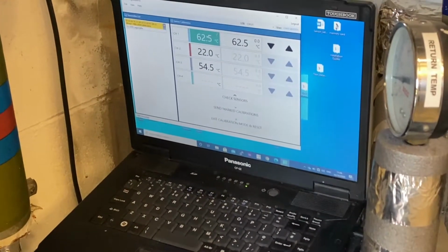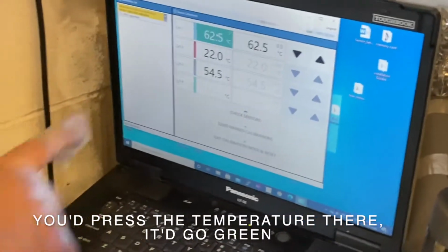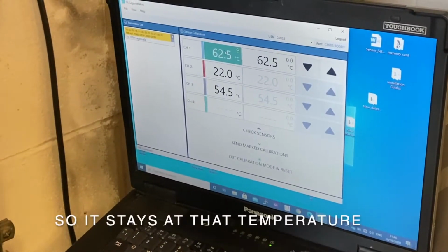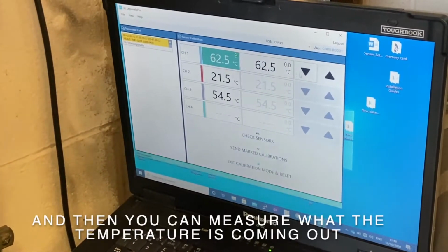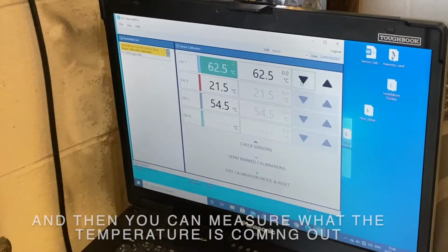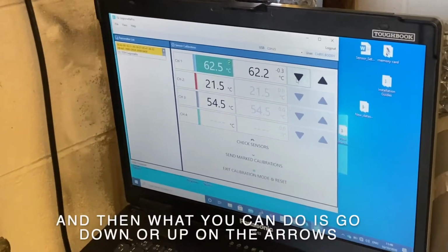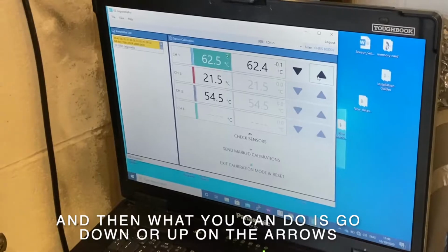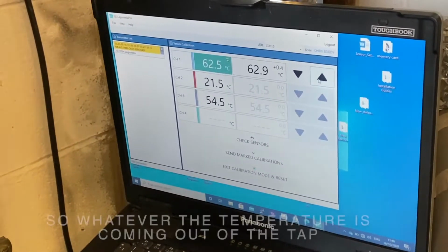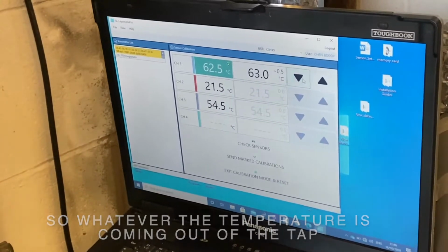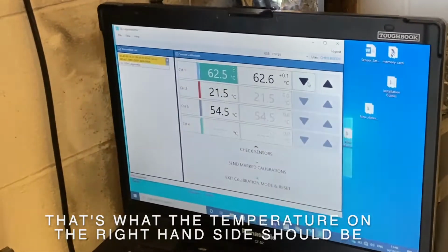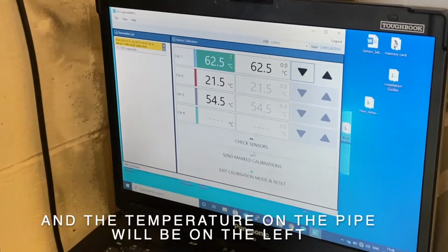So what you do is you press the temperature there, it would go green, so it stays at that temperature, and then you can measure what the temperature is coming out of the tap at that same time. And then what you can do is go down or up on the arrows to put in the offset. So whatever the temperature is coming out of the tap, that's what the temperature on the right hand side should be, and the temperature on the pipe will be on the left.